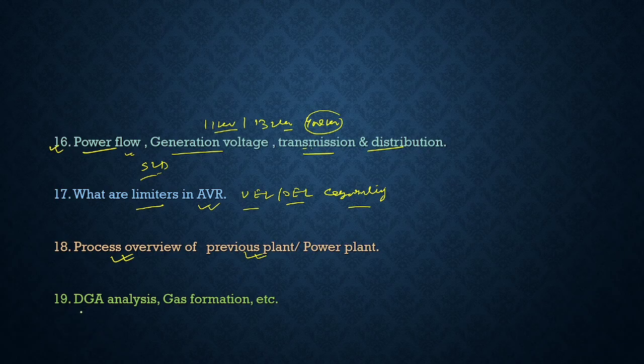Again, the next question was DGA, dissolved gas analysis, gas formation inside a transformer. In the oil and gas sector, these parameters are maintained every 1 or 2 years. They take a sample from the transformer, and they check the DGA, dissolved gas analysis, of the oil. So you can have an idea about the DGA. What are the gases formed: H2, CO, CH4, C2H2, C2H4, C2H6. These are the gases that form. Acetylene C2H2 is one such gas. These are flammable in nature. So you can discuss all these things with the interviewer.